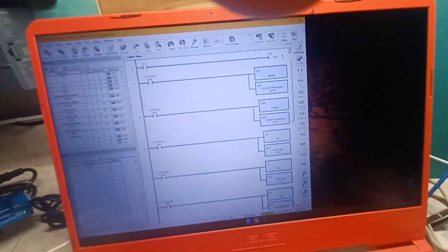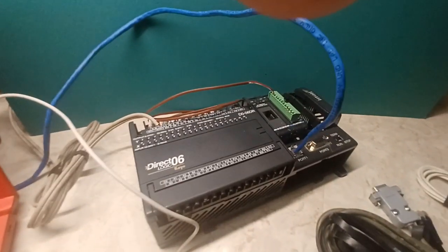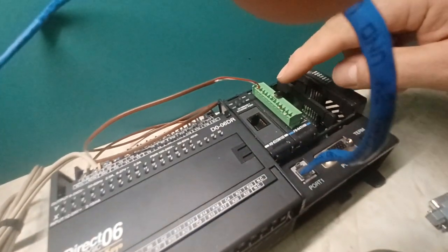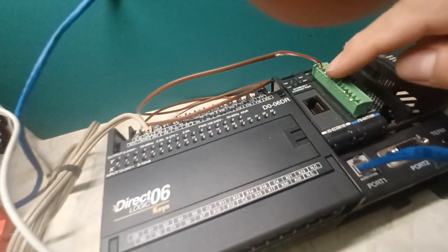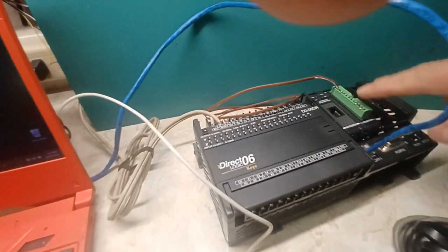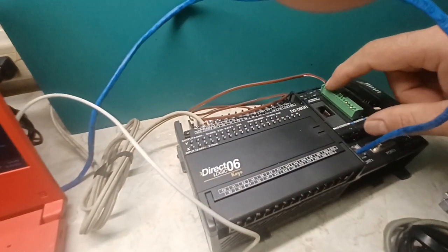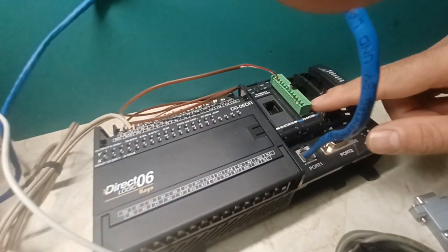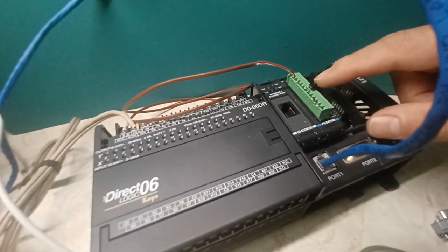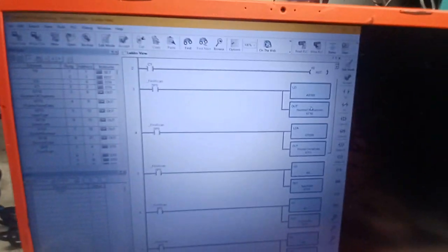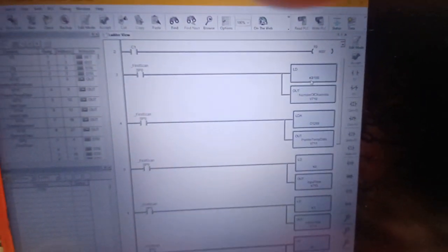And all these are settings, it tells you the number of channels. I'm only using one thermocouple, and all the other minus terminals on the other channels are all jumpered together, because that's what the manual said. To minimize noise levels, you need to make all the negative terminals on the channels common, and then there is an LM35 as a cold junction device. So this is why only one channel, and the values are going to be displayed in binary format, because you can opt for BCD.